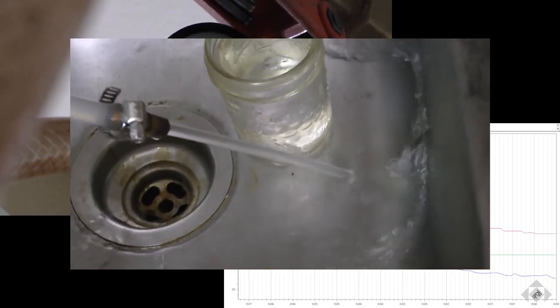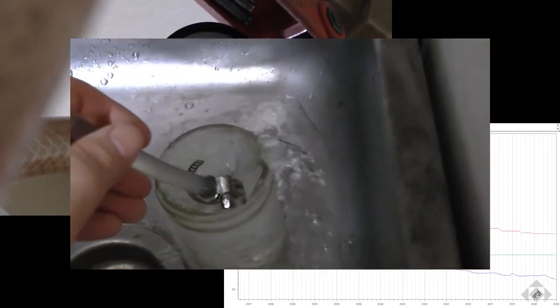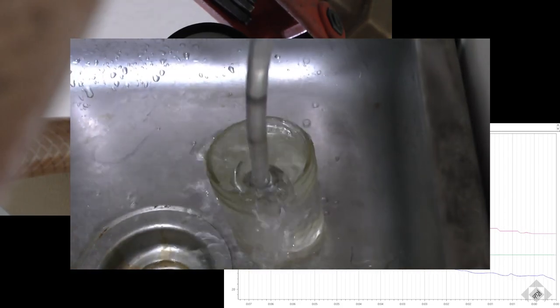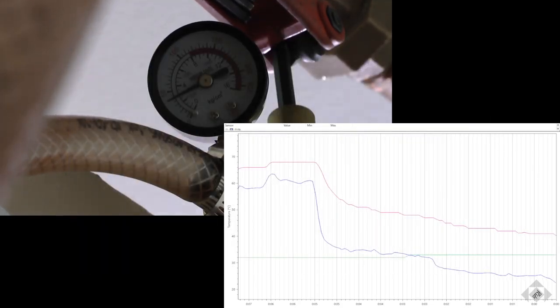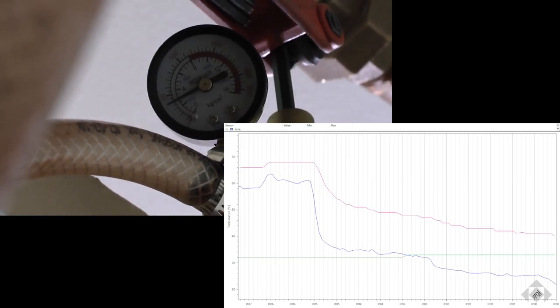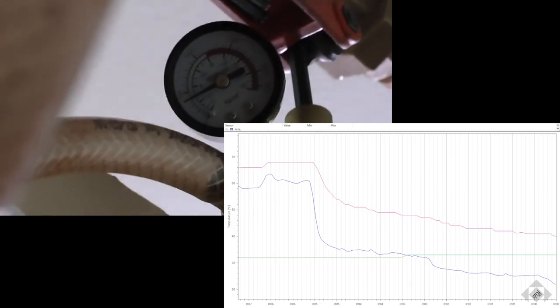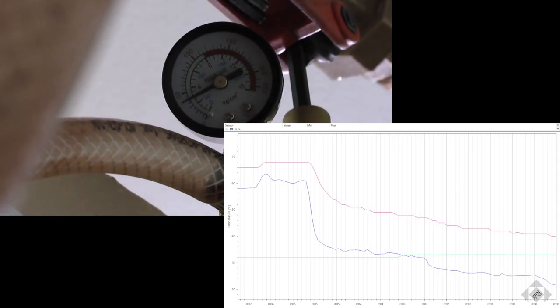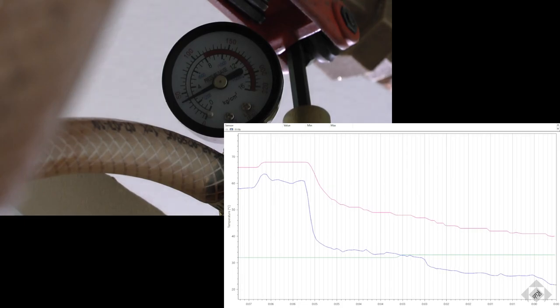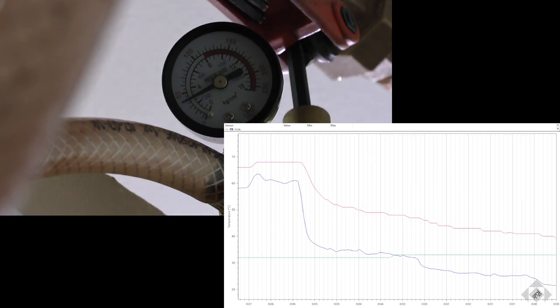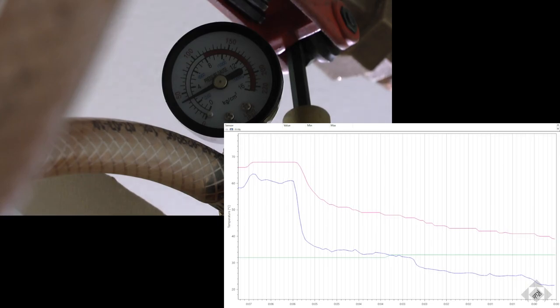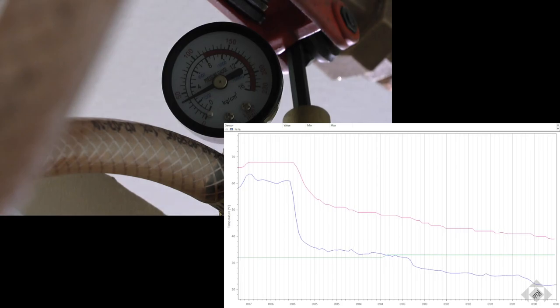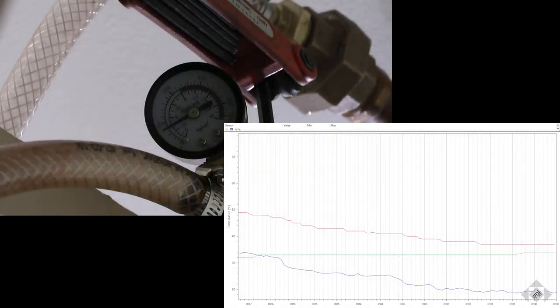Now we're at full power. That's 60 psi through a half inch main into a half inch nylon reinforced plastic hose through a one inch heating cooling coil through the PRV that should be almost wide open then through a quarter inch flexible, I think this is a polyurethane line, some other plastic, who the fuck cares. So that 60 psi that you have on that pressure reducing valve is just the back pressure that is coming from the reduction from the half inch to quarter inch line that we've seen in that manifold inside the computer and we've stabilized at about 40 degrees celsius.